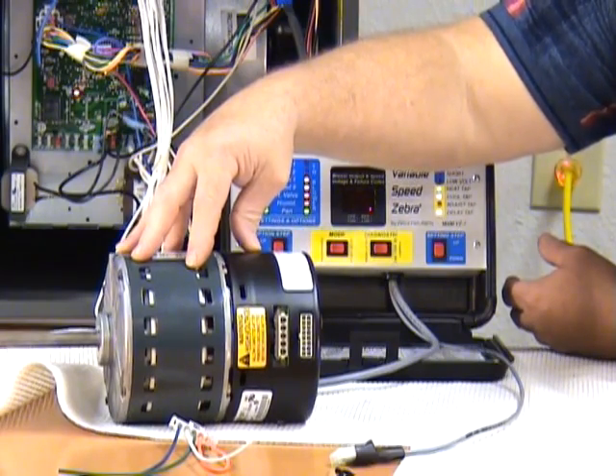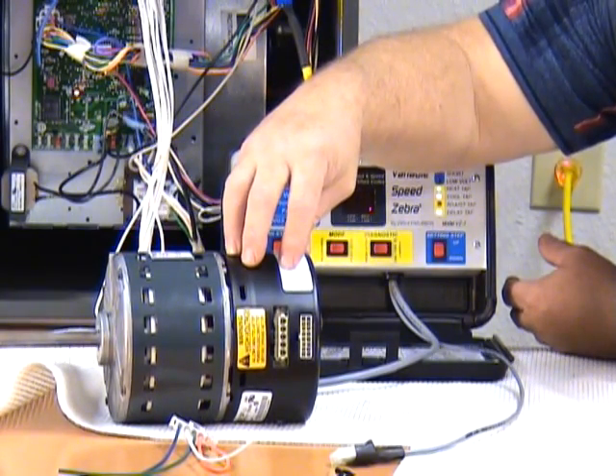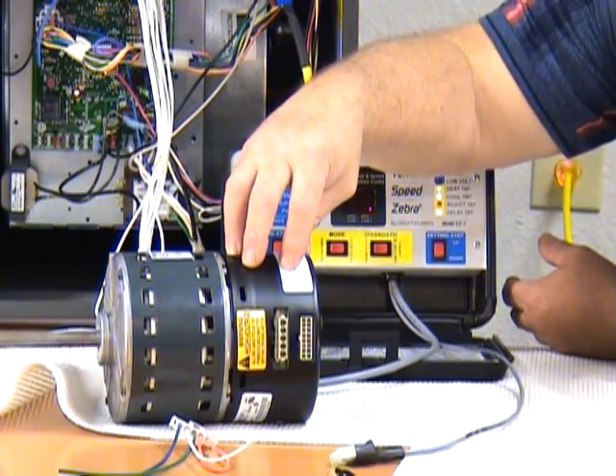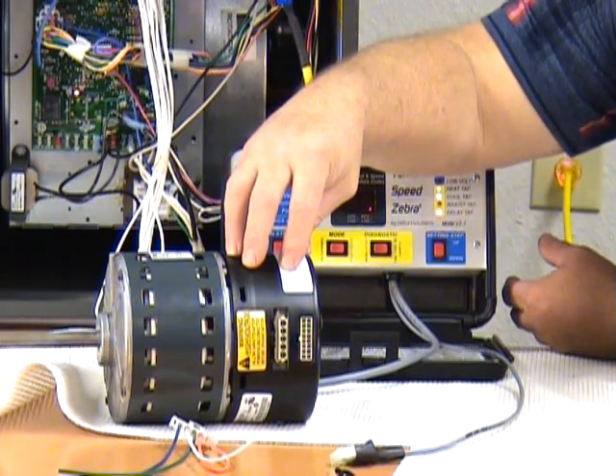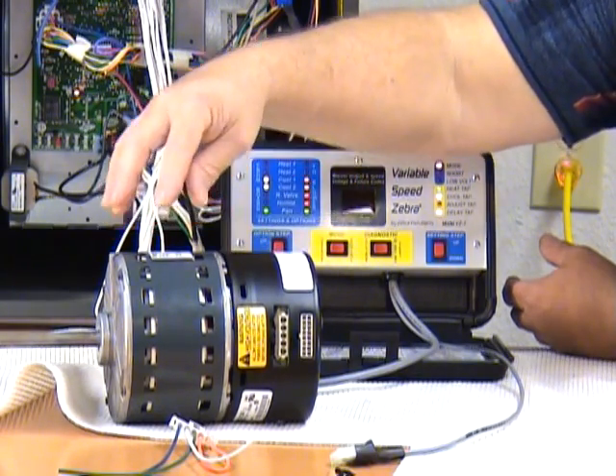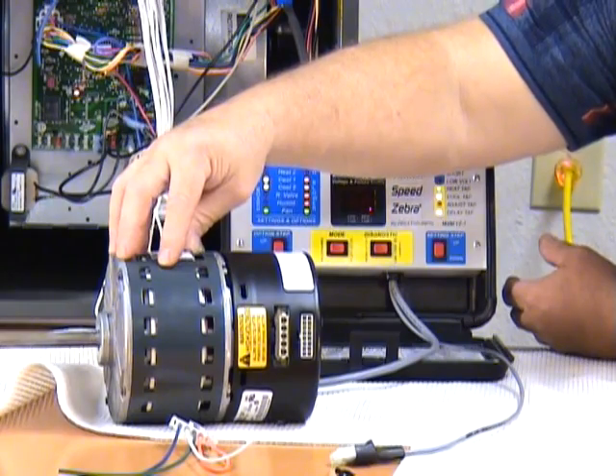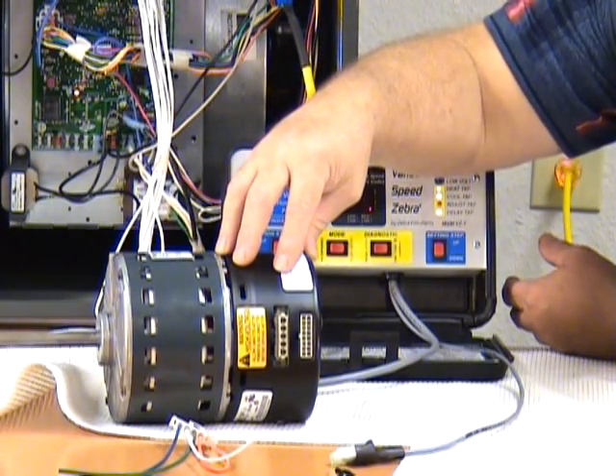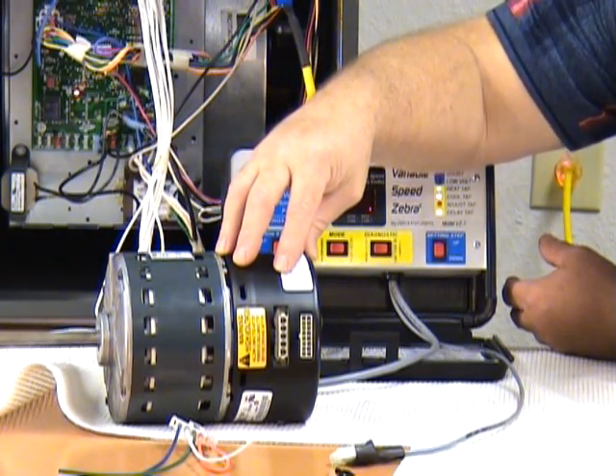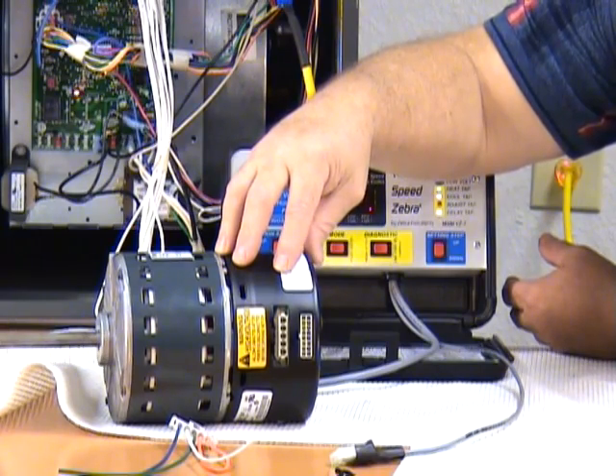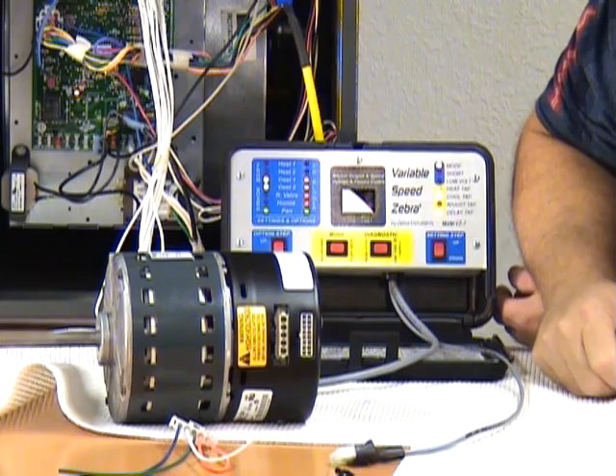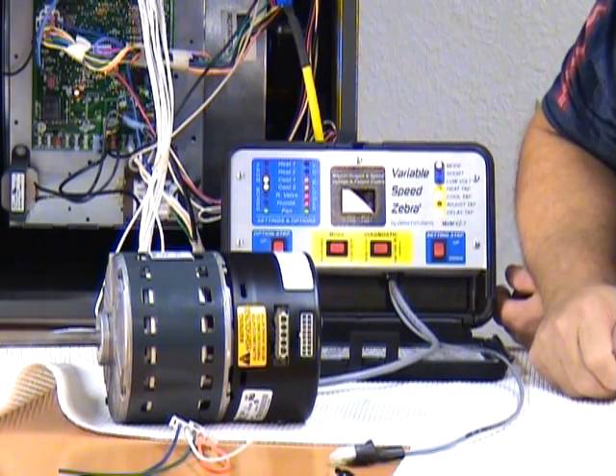Many manufacturers allow you to replace just this section of the motor if it's bad. So the next step you want to do is to determine which section of your motor, the winding section or the electronic module section, actually has the problem. The first thing to do is to shut off the power to your furnace completely, probably best at the circuit breakers. Then remove the motor.